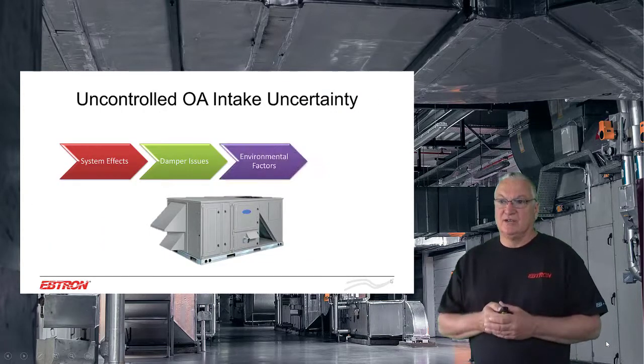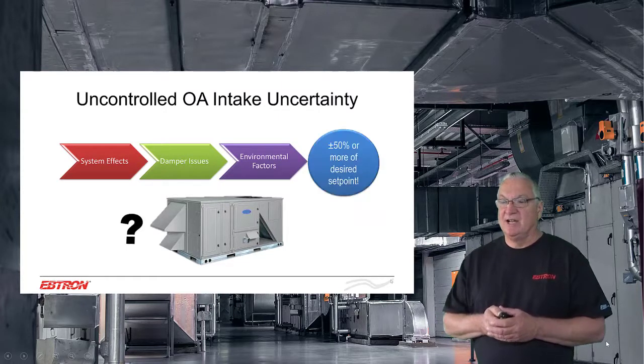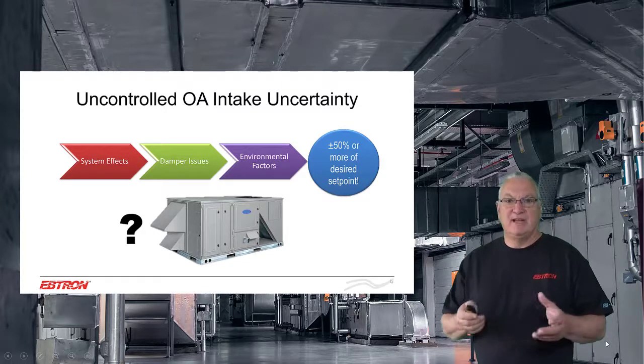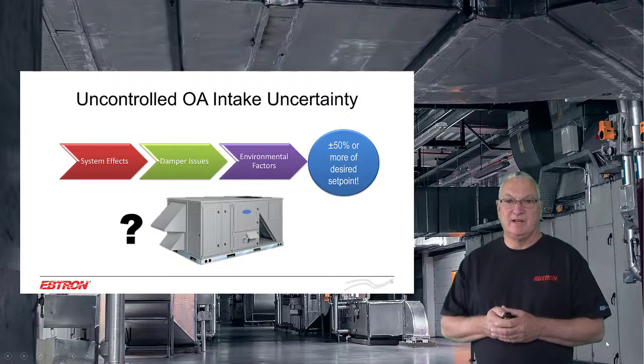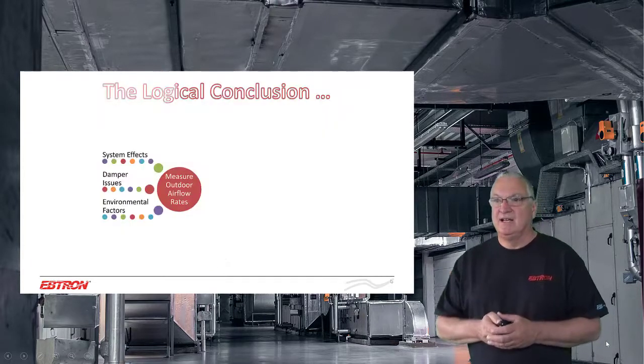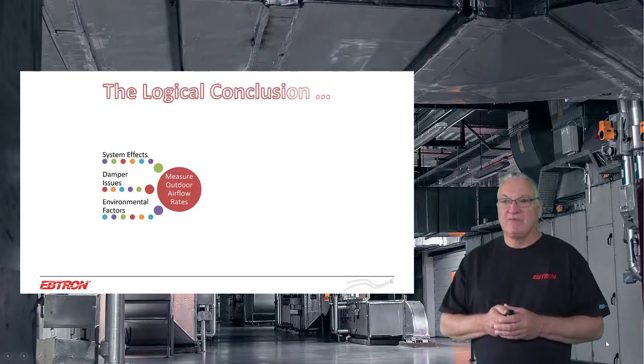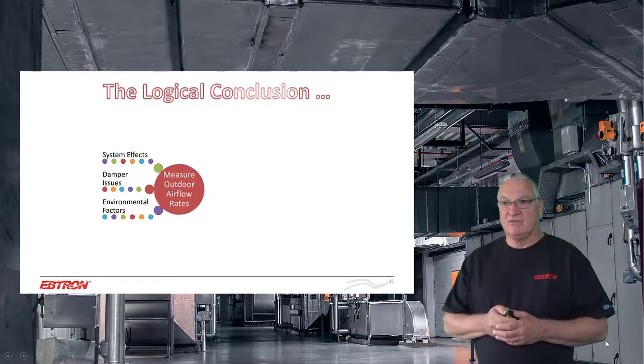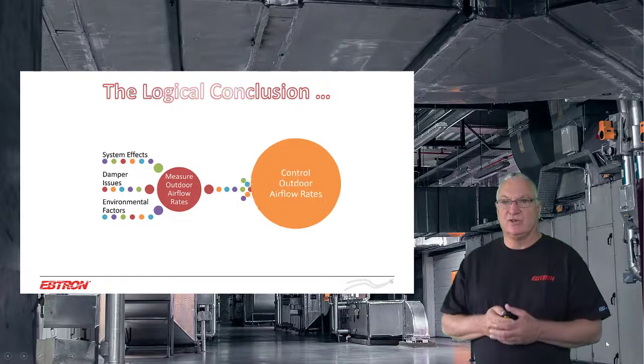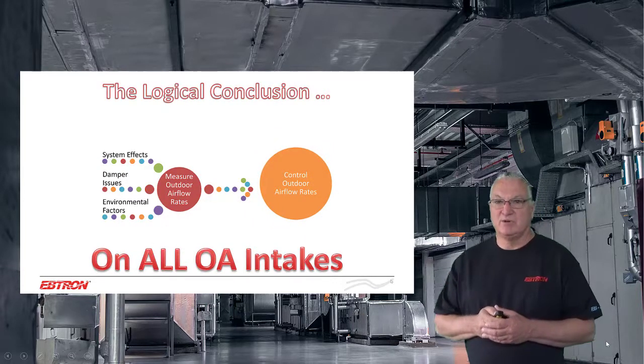We're going to show you that uncontrolled outdoor air intake flow rates — which is the bulk of what we have right now — has a tremendous uncertainty of at least 50 percent of setpoint, and in many cases even more than that. Hopefully, we get the logical conclusion to everybody that it's not just about measuring outdoor air flow rates, but actually controlling them, on all systems.